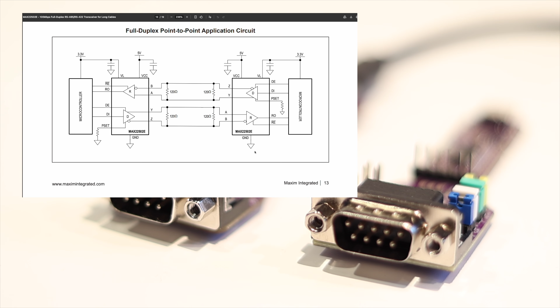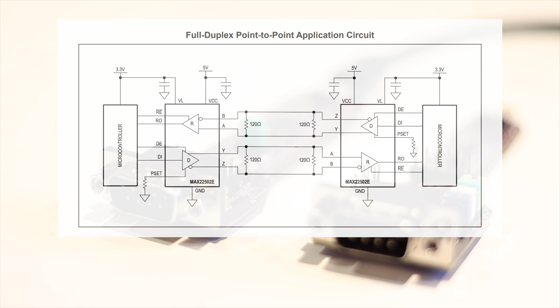RS-422 is often used in factory automation systems, long-distance wired sensors, and it's typically rated at 10 megabits per second, which is pretty cool for two pieces of wire wrapped around each other. It supports one transmitter talking to multiple receivers, which is useful for distributing data from a central controller. But if you need two-way communication, you need two pairs of wires.